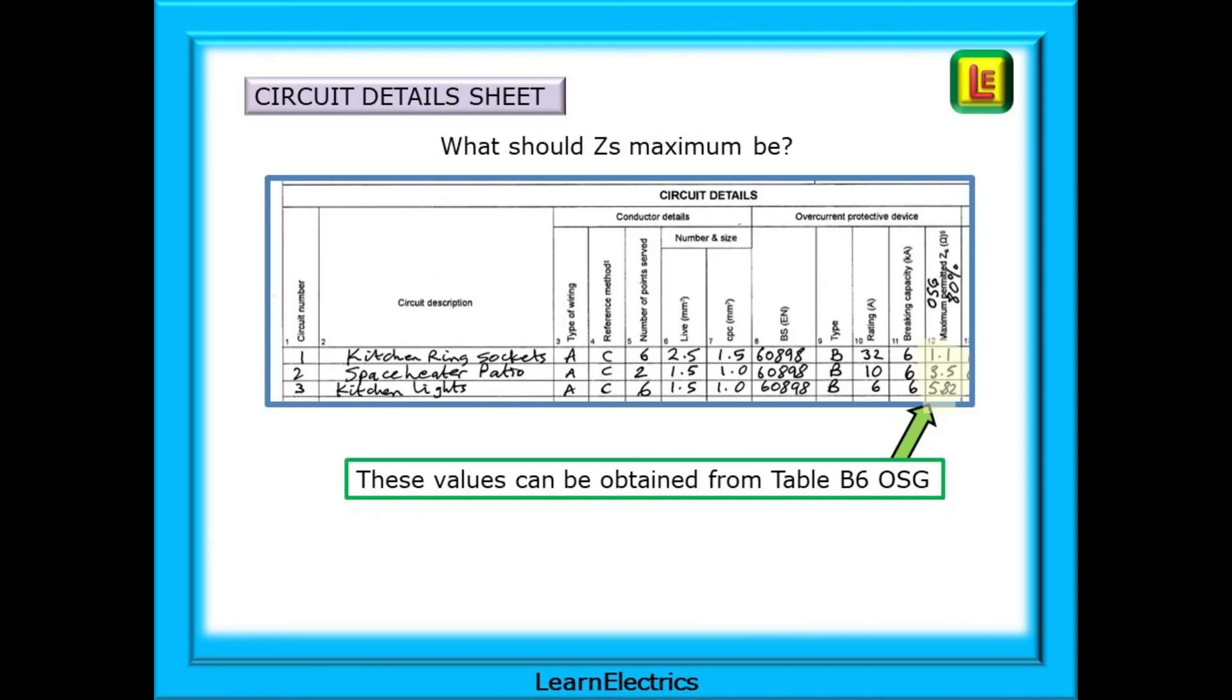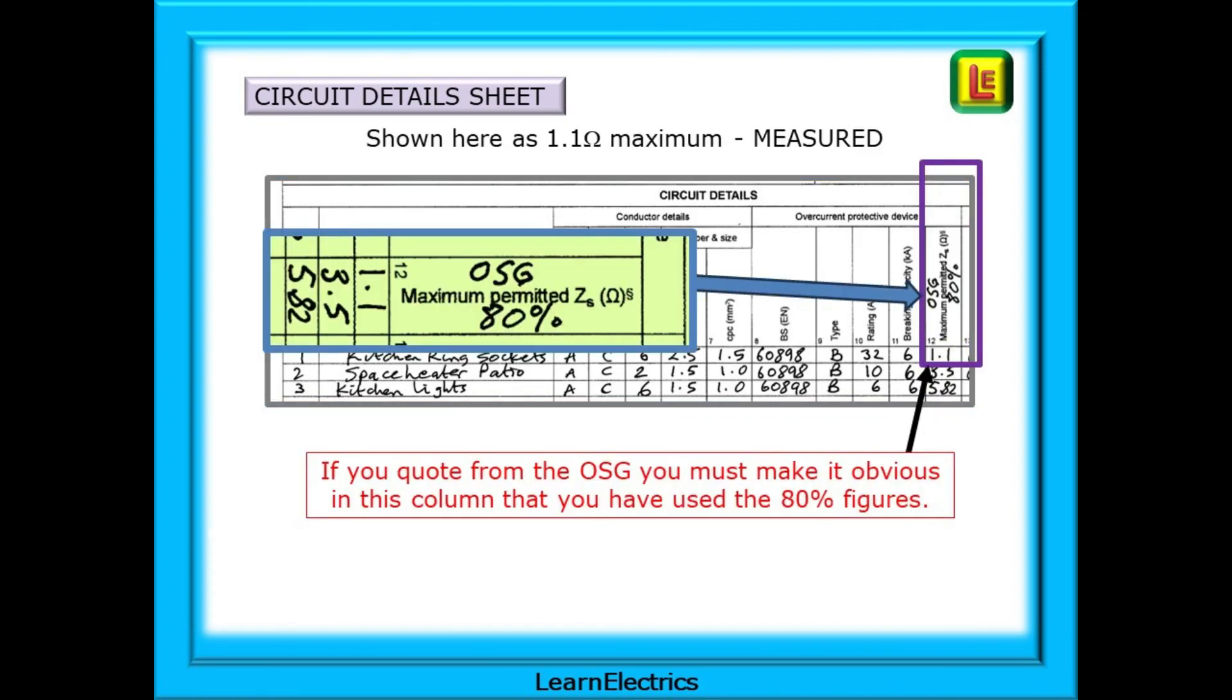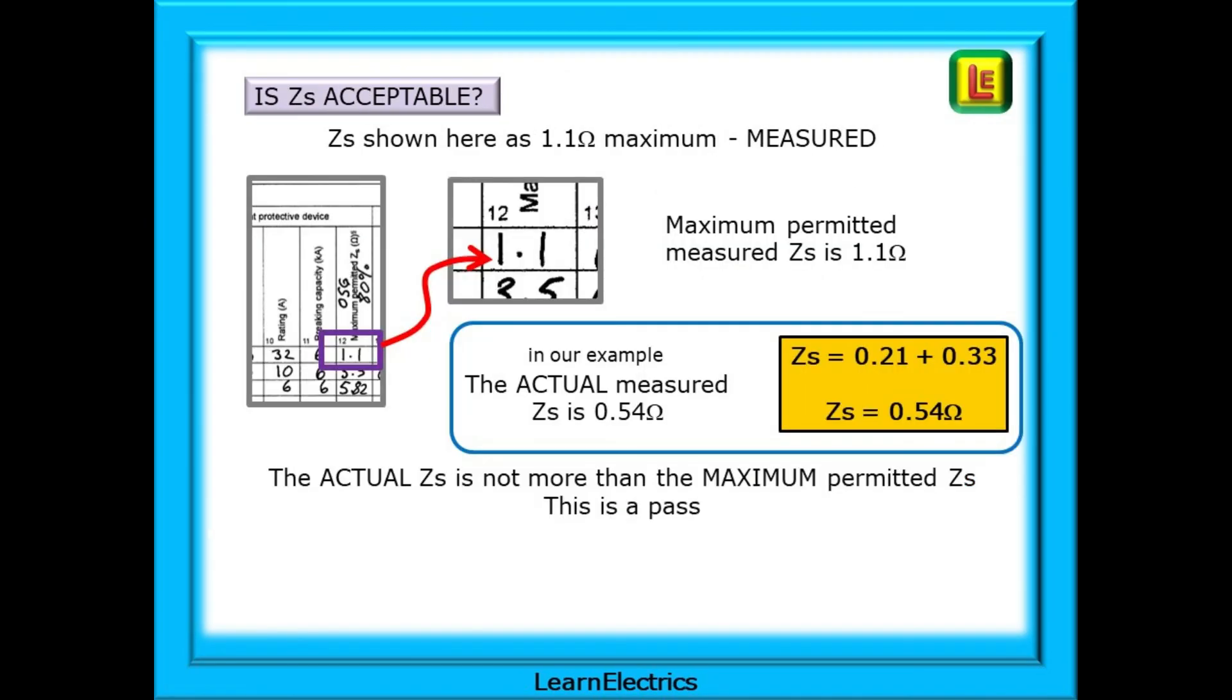We should compare this now to the maximum permitted ZS that we found in table B6 of the on-site guide, and also written on the circuit details sheet as shown here. I always quote from the on-site guide, so I always make it very obvious to any reader of my test data that this is an 80% figure taken from the on-site guide and not the 100% figure from the regs book. Maximum permitted ZS is 1.1 ohms, and we've measured and calculated ZS to be 0.54 ohms. This is a good result. 0.54 ohms is less than 1.1 ohms, so ZS is acceptable.